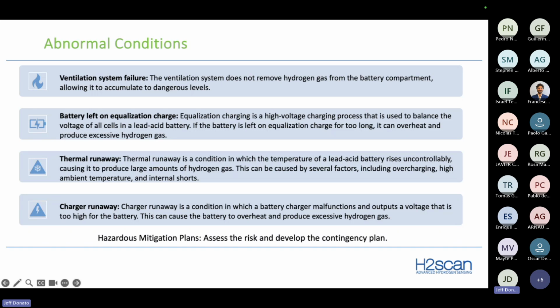types of conditions. So we have seen where batteries are accidentally left on equalized charge. So can the gas purge system, or the ventilation of the room, handle that sort of condition? Also, thermal runaway, if there's a condition that maybe leads to that, which leads to gassing. I'm going to give you an example I don't have a slide on it, but I'm going to tell you verbally about a situation that happened with valve-regulated lead-acid batteries with thermal runaway. And then, of course, charger runaway being a very rare condition, where the charger ramps up to maximum charge voltage. And so we're required to have a mitigation plan for each one of these conditions.